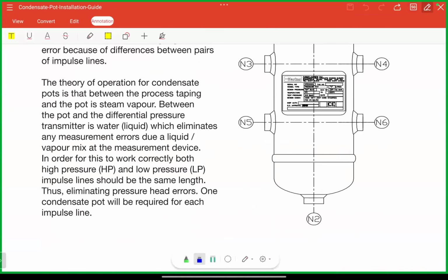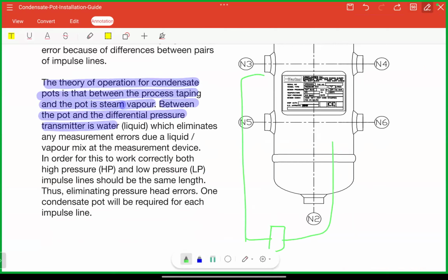What is the theory of condensing pot? Between the process tapping and the pot is the steam vapors. Between the pot and the differential pressure transmitter is water. So one side what is there? Steam. One side you are having water. So if you are allowing steam from one side to act on the DP transmitter and one side you are allowing the water to act on the DP transmitter, do they have same density? No sir, this side is steam, and this side is your water. They don't have the same density. So how is your DP transmitter going to measure? DP transmitter is supposed to measure fluids with the same density. Then only there will be logical analysis of the level or something like that, isn't it?